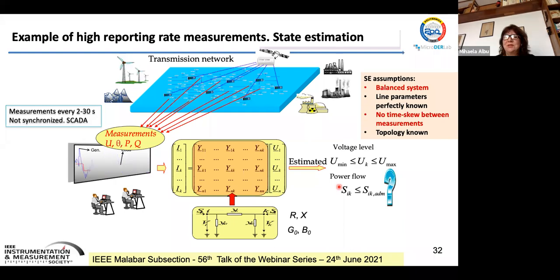Usually, as I'm sure that you know, the classical state estimators, which are run at the system level, use SCADA provided measurements, not synchronized, however, timestamped, but not always using a synchronization time tag. And they are provided at time intervals of 2 to 30 seconds.